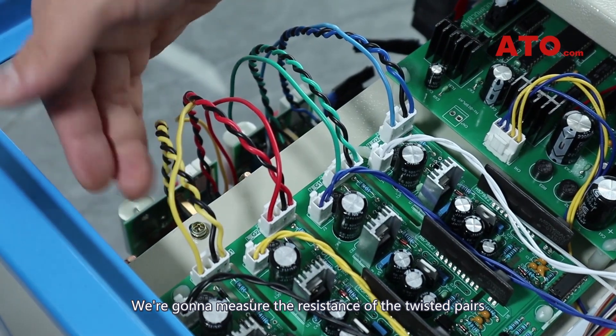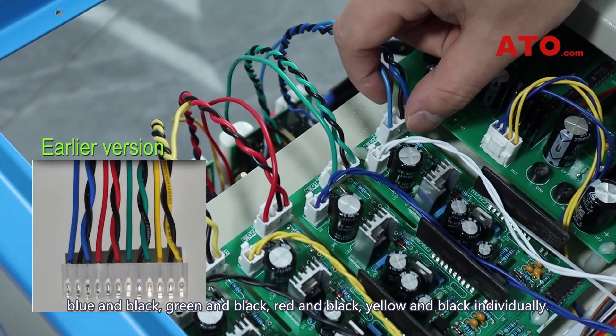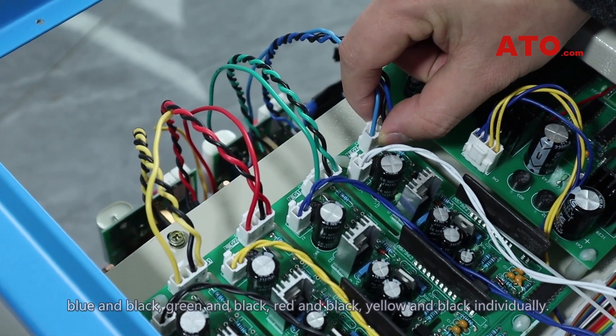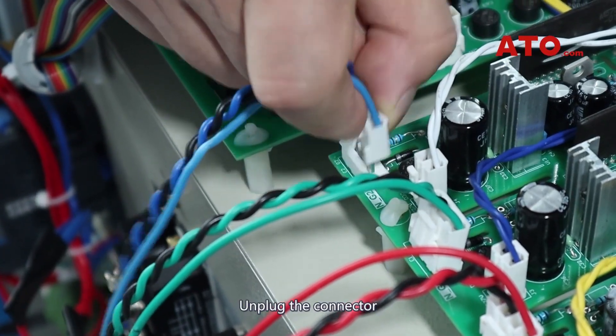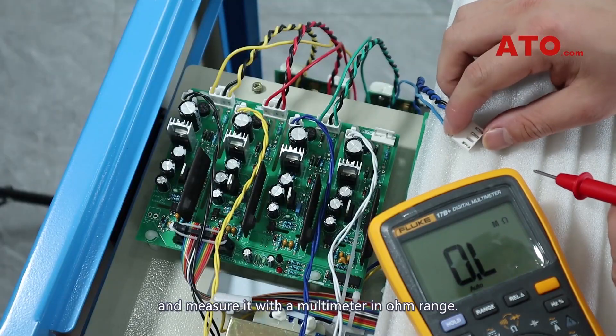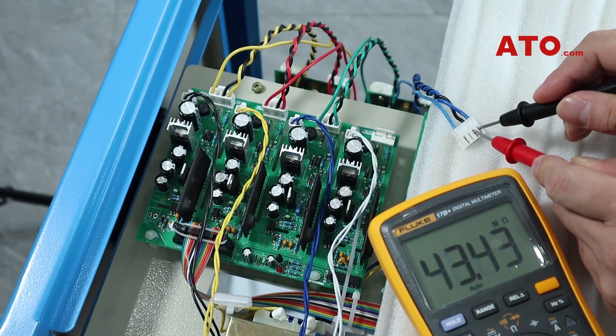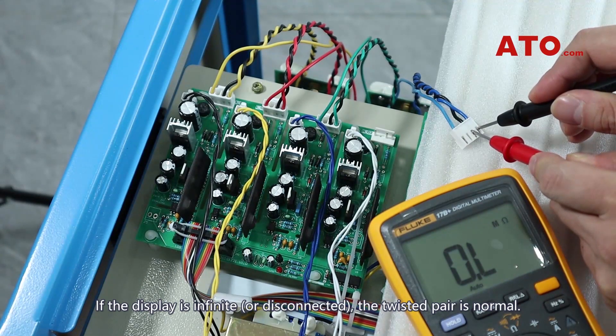We're going to measure the resistance of the twisted pairs — blue and black, green and black, red and black, yellow and black — individually. Unplug the connector and measure it with a multimeter in ohm range. If the display is infinite or disconnected, the twisted pair is normal.